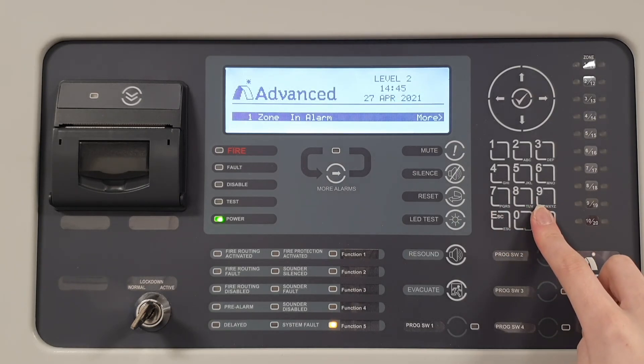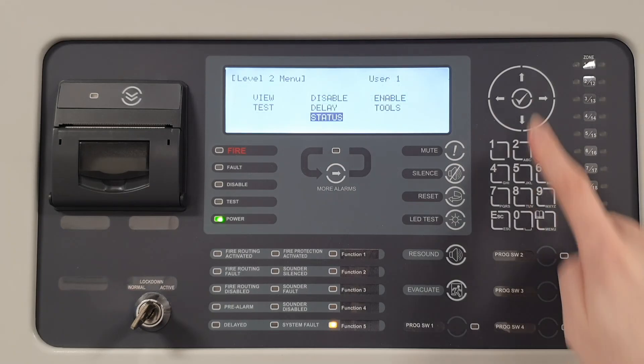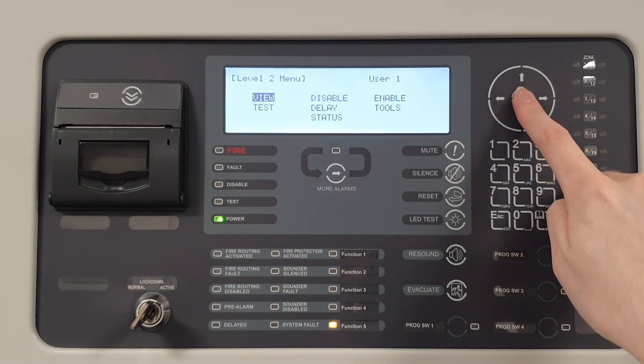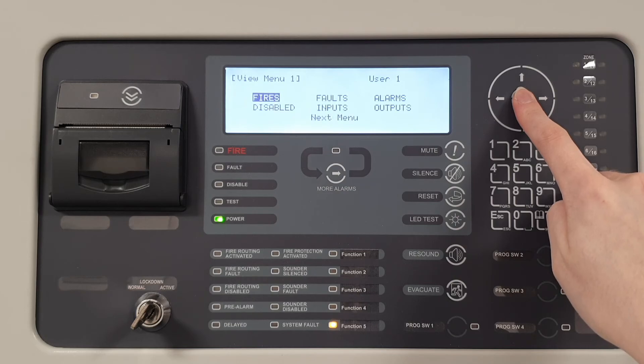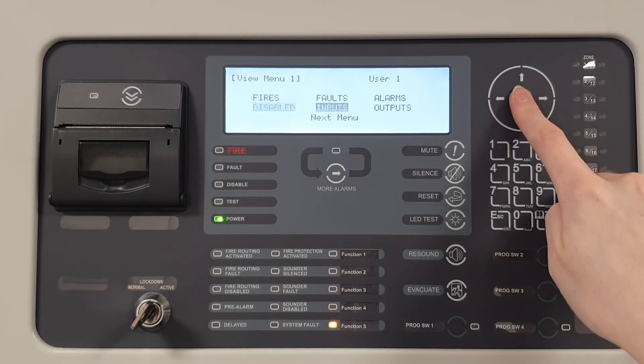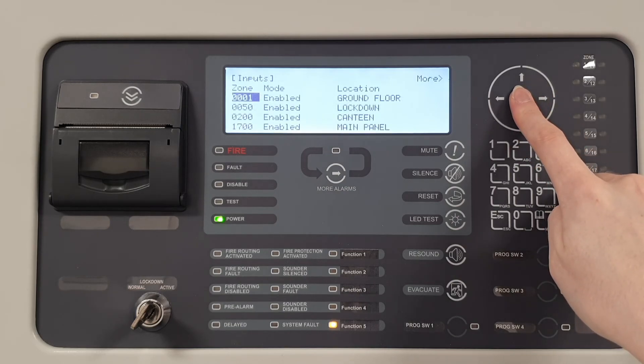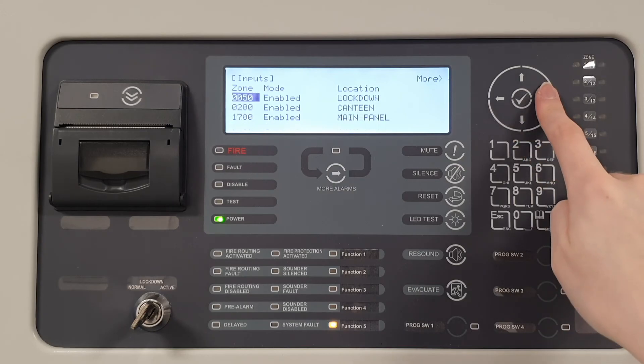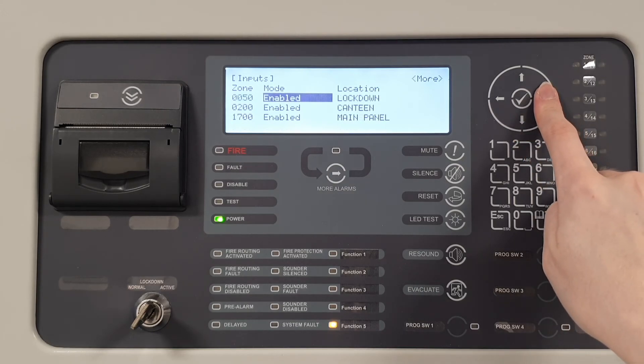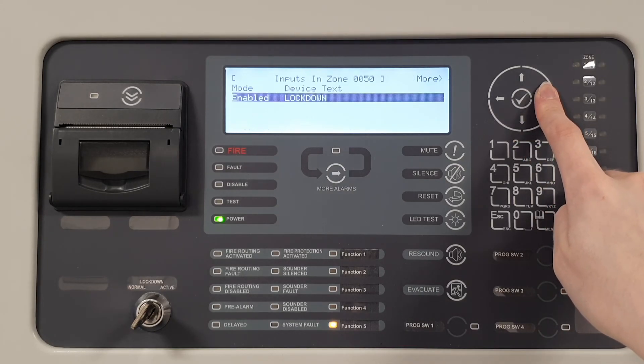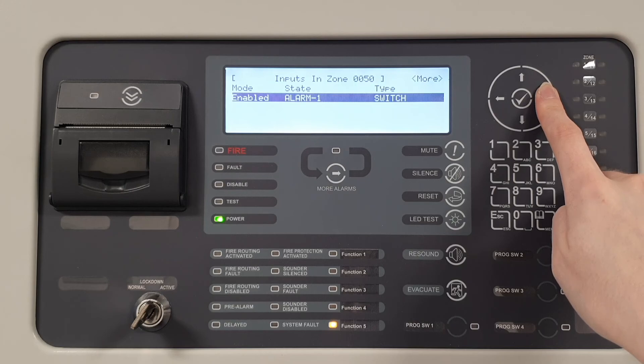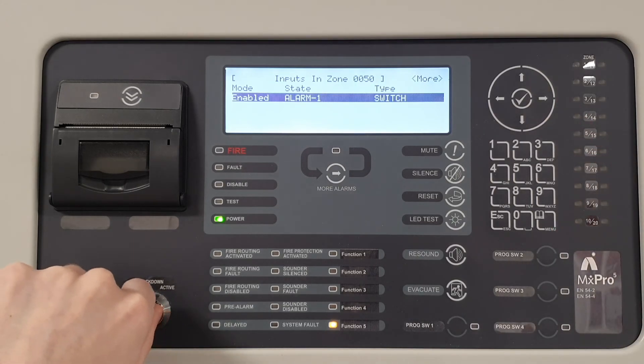To view the state of the input, go to view and then inputs through the panel menu. Scrolling to the right on the zone for the lockdown input will show the state. As the key is still in the active position, the state for this input is alarm 1.